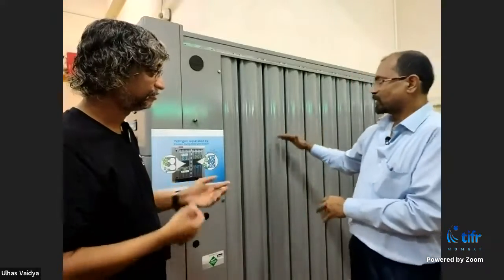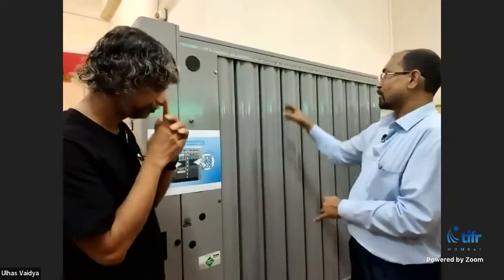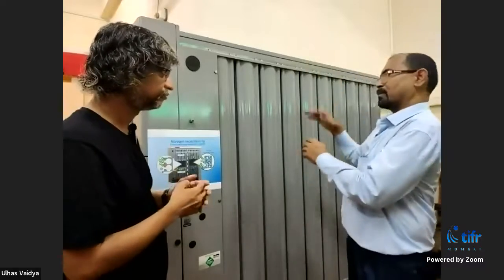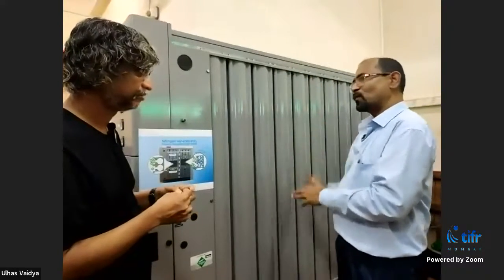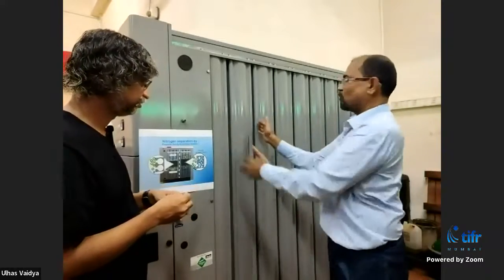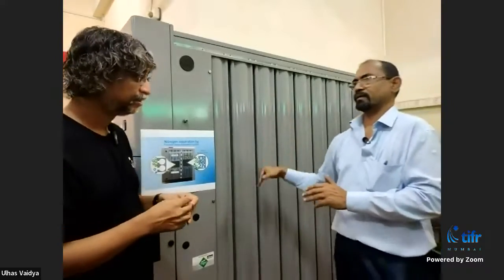After saturating the whole column, nitrogen flows backward and flushes out the saturated oxygen. Meanwhile, another set of filters comes into picture to purify the air. So basically we have two sets of these filters - the dry air under pressure goes through it, oxygen gets stuck onto the molecular sieve, and nitrogen goes through, until after about 4 minutes it's saturated.